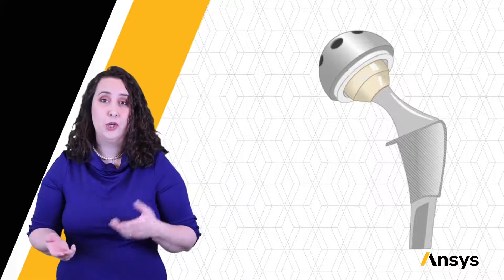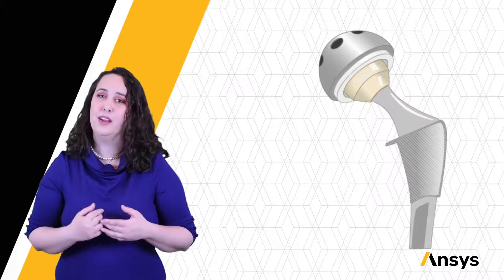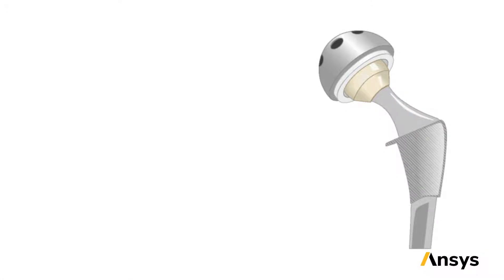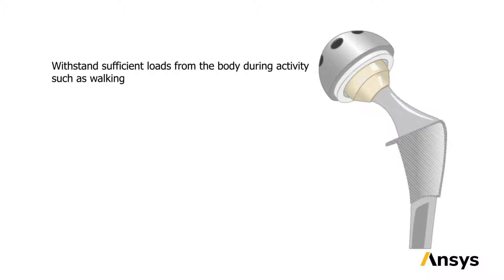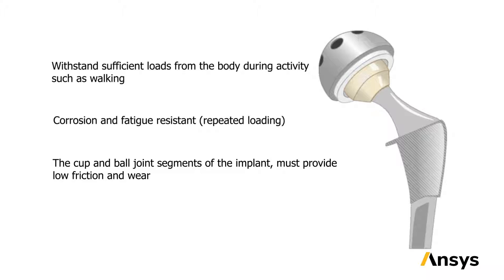The reasons this might be implanted are vast: old age, a bad fracture, arthritis. Maybe you know someone in your family or group of friends who's needed their hip replaced. Whatever the reason, this hip implant must be able to withstand sufficient loads from the human body during activities such as walking. It must be corrosion and fatigue resistant — fatigue meaning withstanding repeated loading. The cup and ball joint segment of the implant must provide low friction and low wear. If I'm having this implant put in because I lost my natural cartilage in my hip due to arthritis, I want to make sure that my new joint will move smoothly.